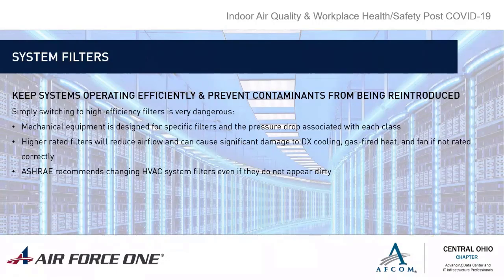The catch-22 is a lot of the recommendations were for higher rated filters such as HEPA or MERV 13. What we like to say, and the reason we developed this whole presentation, is that simply switching to high efficiency filters is very dangerous. Your mechanical equipment is designed for a specific pressure drop and a specific filter. So when you replace a filter with a higher rated one, you might actually be doing more of a detriment to your mechanical system than mitigating the spread of COVID-19.